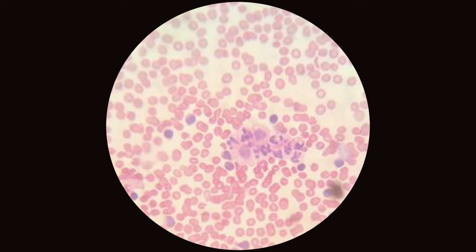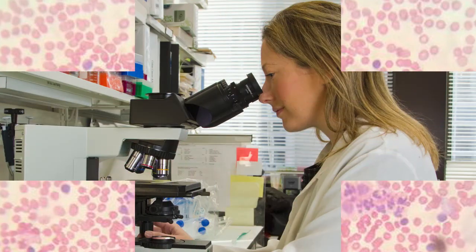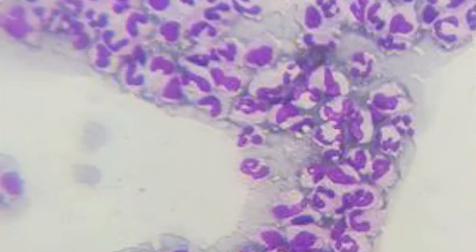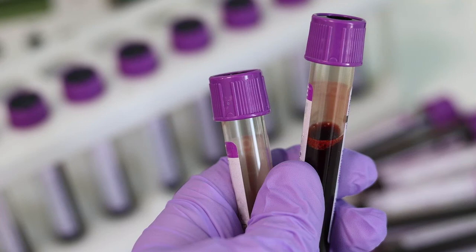Low platelet count. A microclot in the sample or a fibrin clot can use the platelets for clot formation and give a low platelet count. Sometimes it is difficult to identify, and this fibrin clot can block the sample aspiration probes in the instrument.